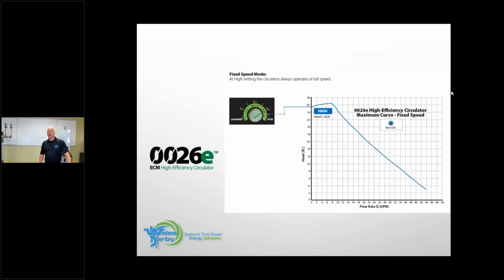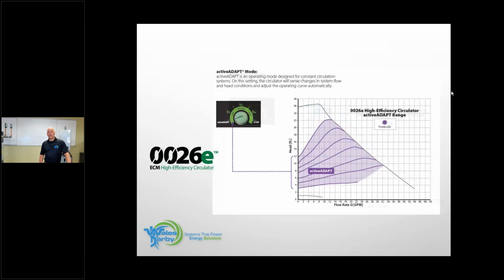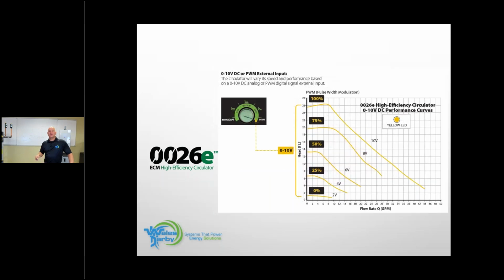These are circulator charts. This one's clean. Let me go to the next one. This one right here shows you the ability of a circulator to make these changes as we call them, holes in the system close. So as zone valves close, that's closing a hole, all right? The more zone valves are closed, the more holes closed, the more we're going to adapt and adjust the flow of that circulator to marry up to the system, okay?